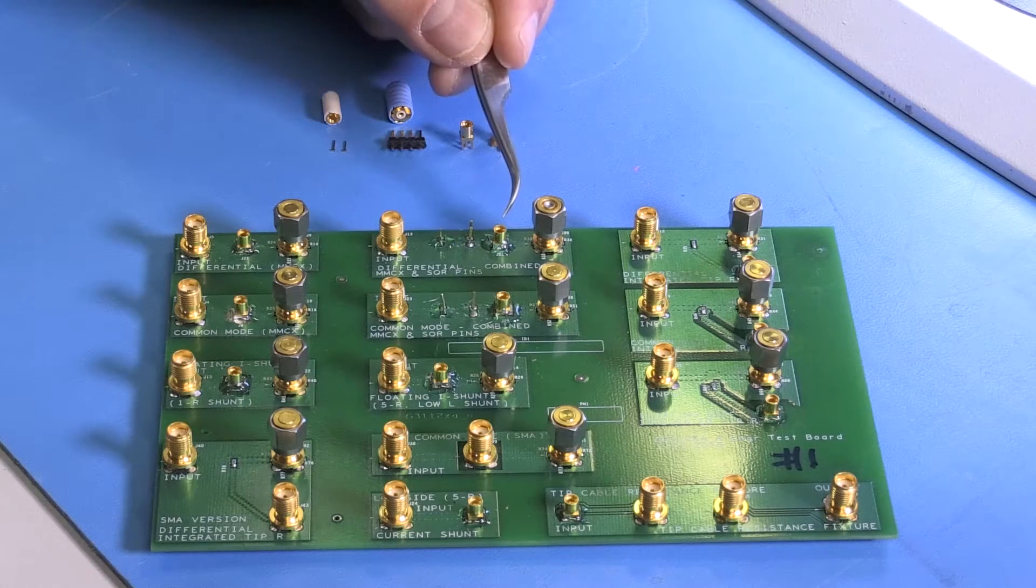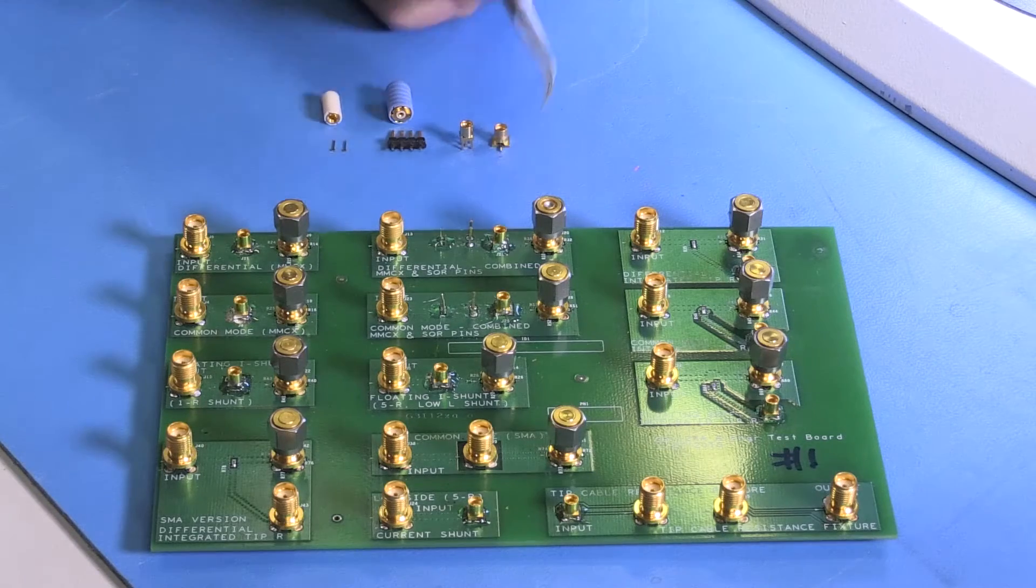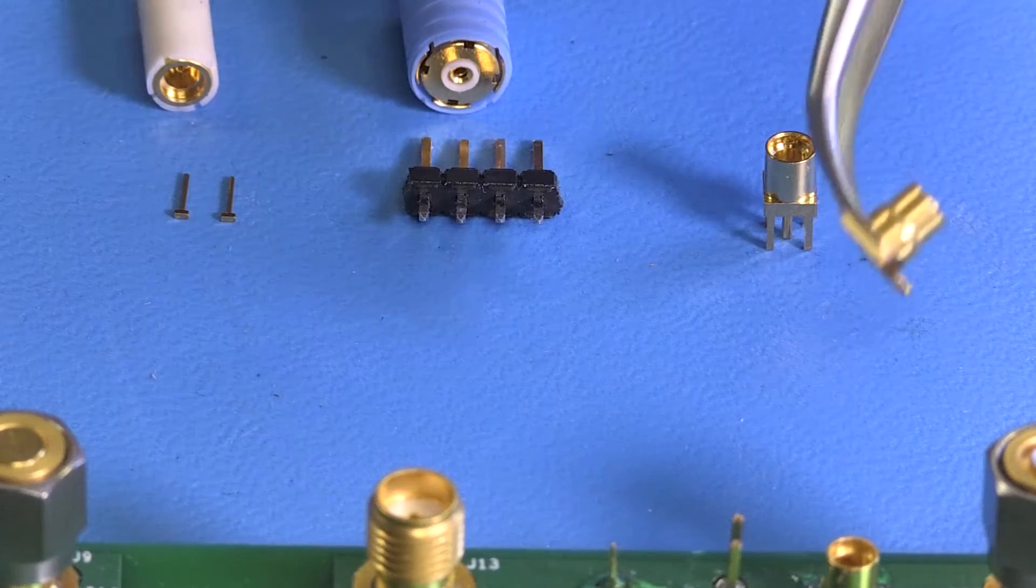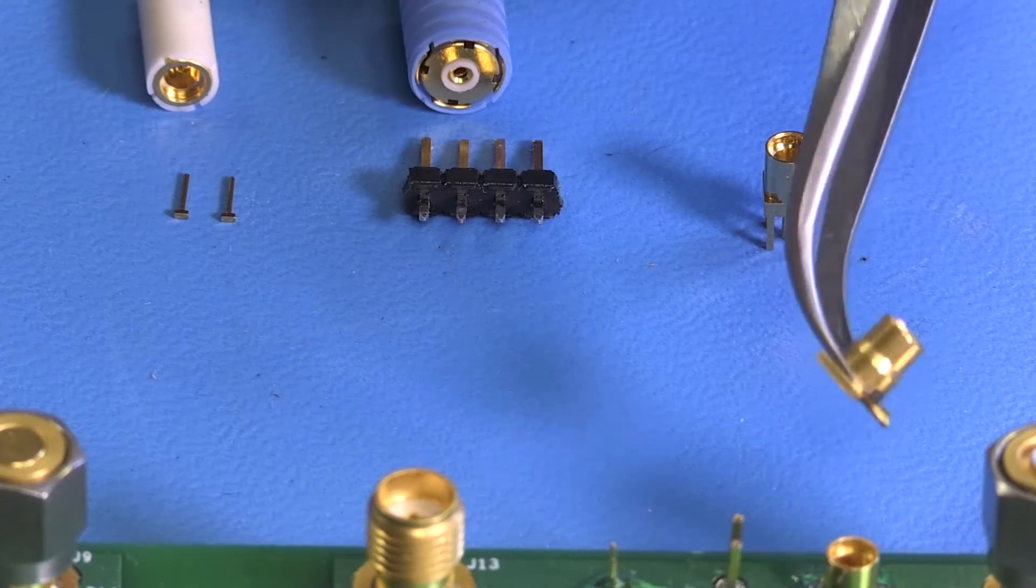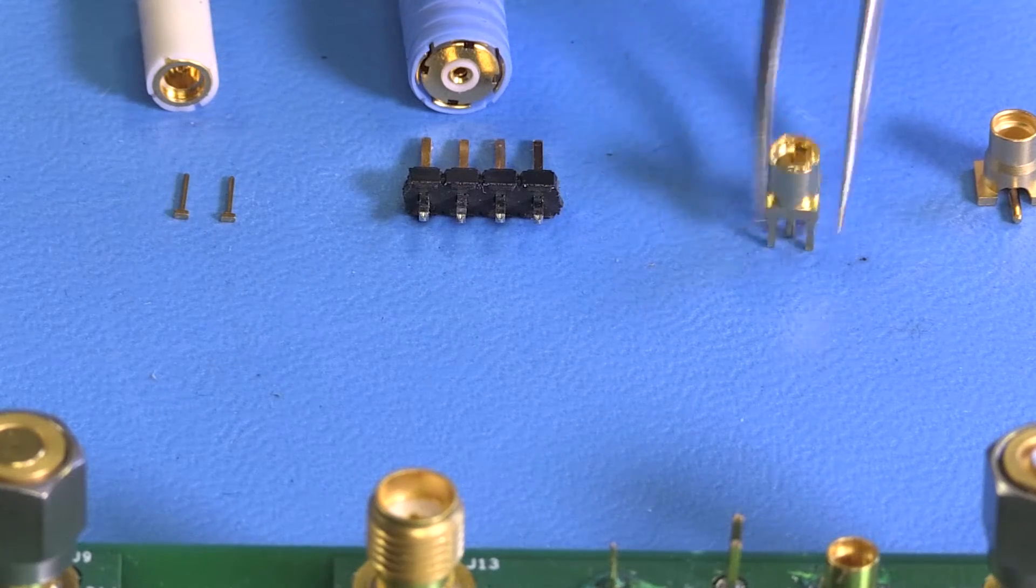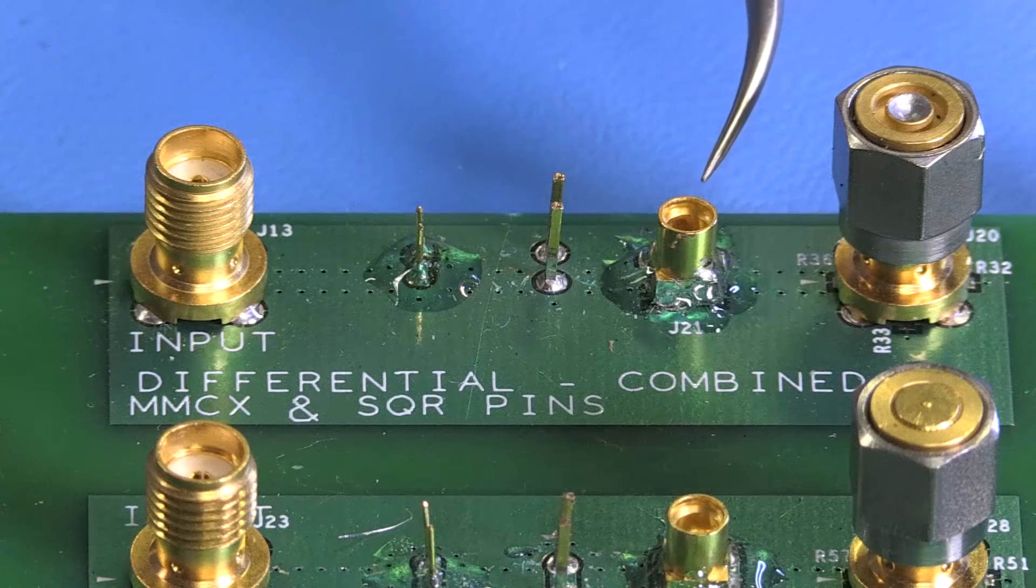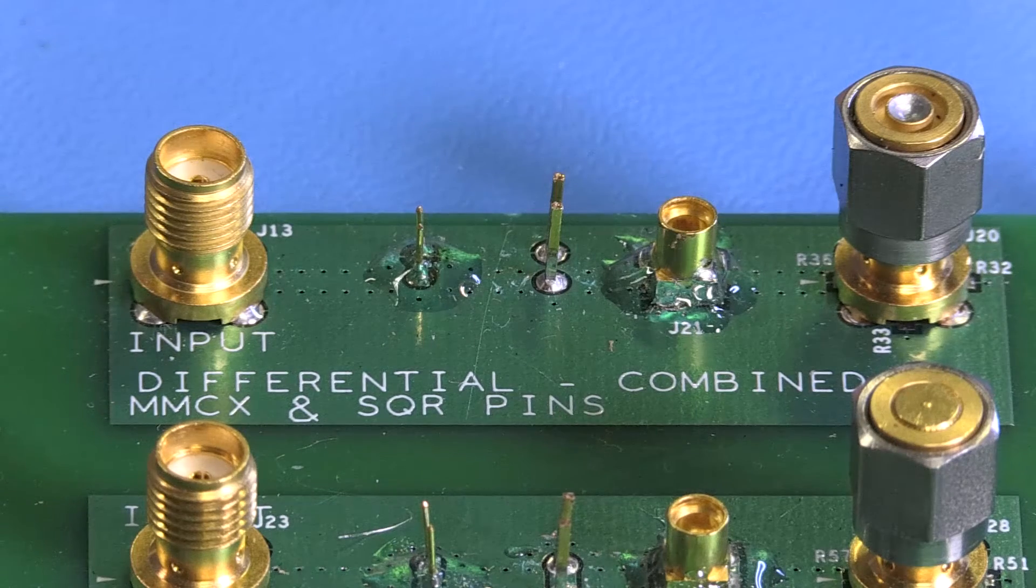We've built this demo board with three different types of connections. The first and highest performance connection method is to design an MMCX connector into your device under test. The MMCX connector is an industry standard connector and is currently available from a number of online retailers at low cost. The MMCX connector has plenty of bandwidth for our application and provides a shielded coaxial environment all the way to the test point, ensuring the highest common mode rejection and the best performance. The best way to use this type of connector is to design it into your test board as a planned test point.